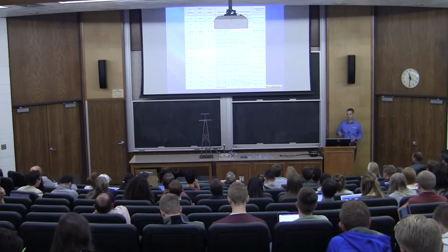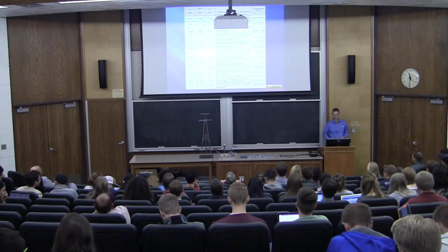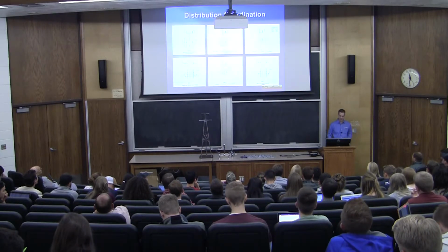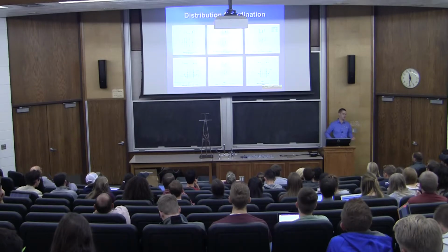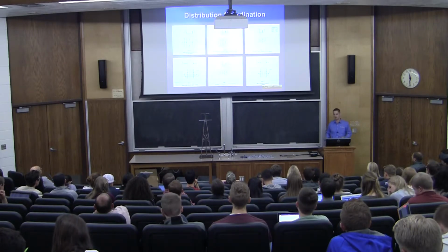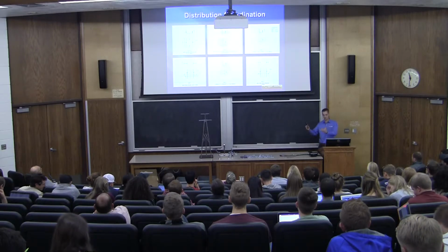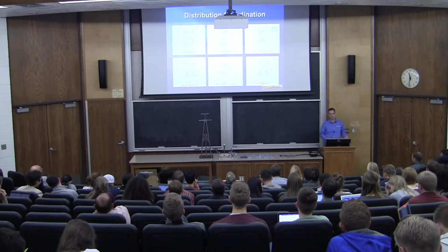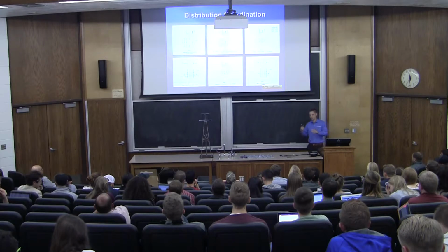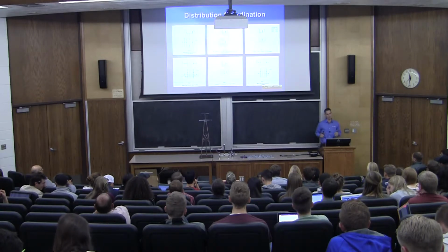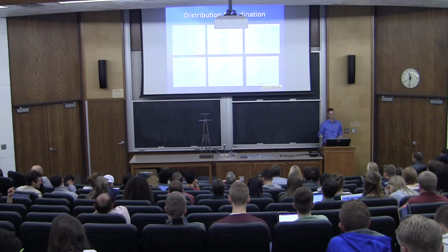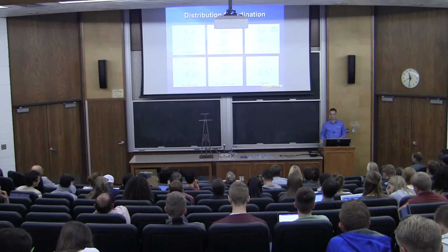So we had to write out a defined scope for every single structure: what are they going to be doing, are they installing new cross arms or new equipment, get that all labeled out. Then we found out the distribution company always deals with wood poles, but we're coming in with steel poles. They have no connections for their existing equipment to a steel pole, because normally they just field drill a couple holes and throw it across the mount. But we can't do that on a steel pole that's being fabricated six months in advance of our construction.